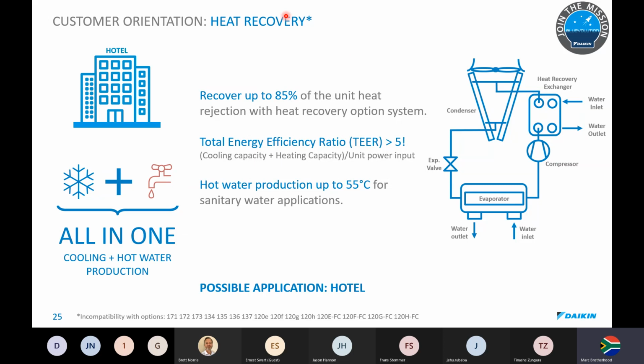This is the heat recovery option available on these chillers, where we produce cooling and take cold water and we produce hot water. So we can recover up to 85% of the unit's heat rejection with heat recovery. So instead of this fan spinning and us wasting the rejected heat, that heat comes straight out of the compressor and goes into a desuperheater, which we call a heat recovery exchanger. And we desuperheat it, but we don't subcool it. We just desuperheat the gas. So by the time it leaves this desuperheater, it's still in vapor form.